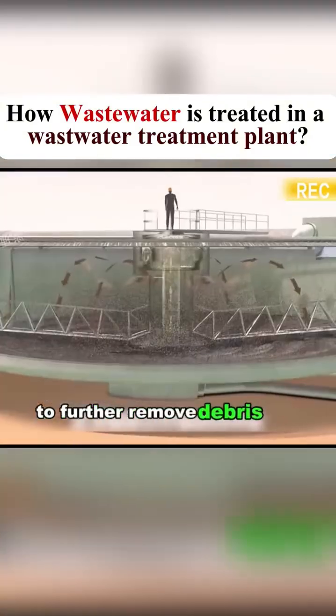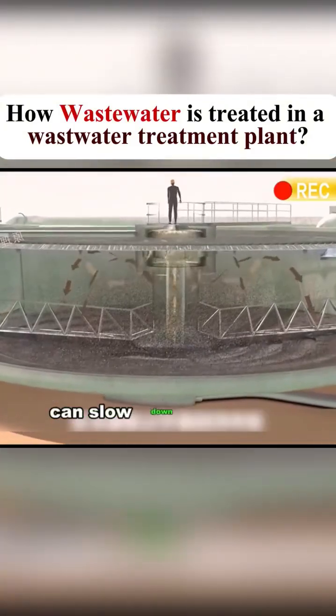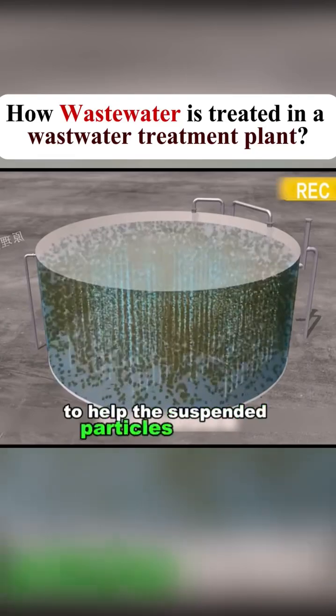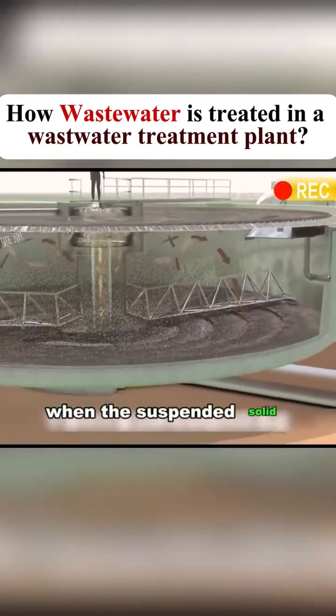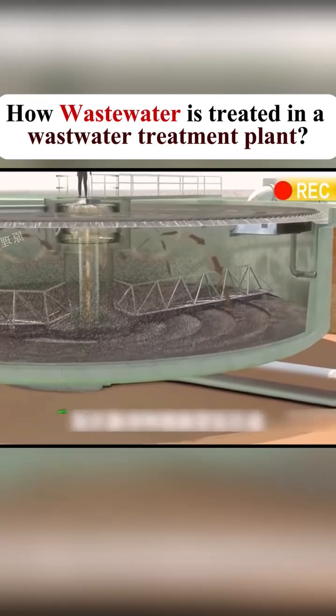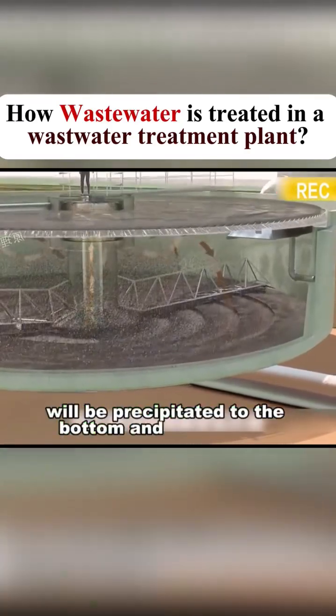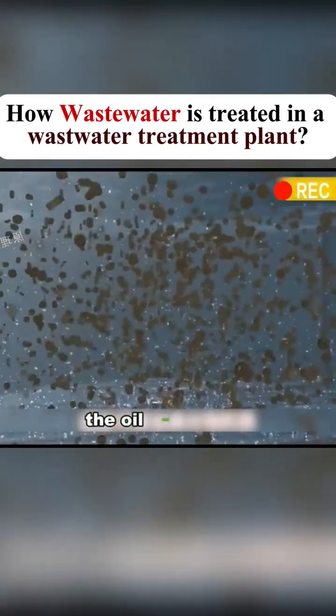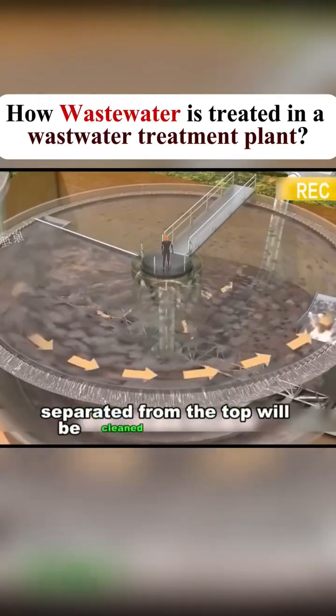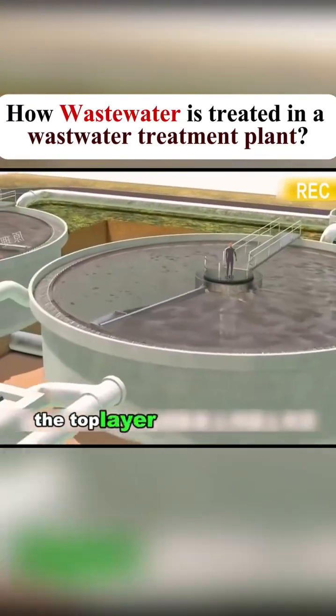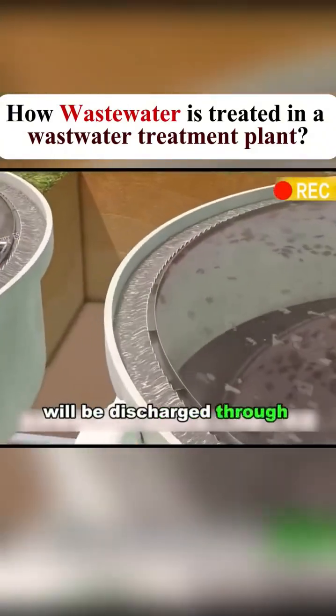Then the sewage from the sand sedimentation tank will enter the primary sedimentation tank to further remove debris. The baffles in the tank can slow down the water flow to help the suspended particles to settle. The suspended solid debris, under the effect of gravity, will be precipitated to the bottom and form sludge. The oil and grease separated at the top will be cleaned by a scraper.